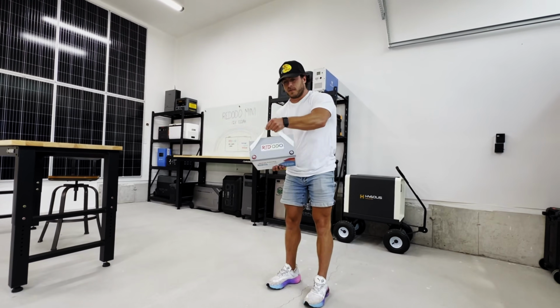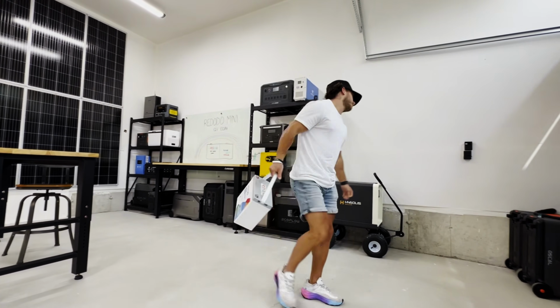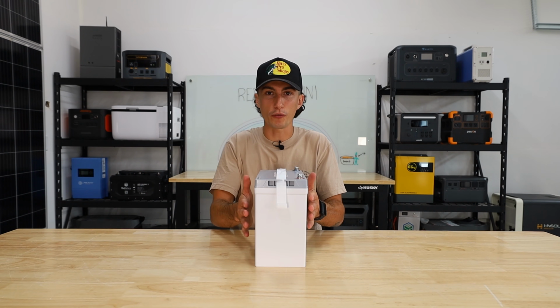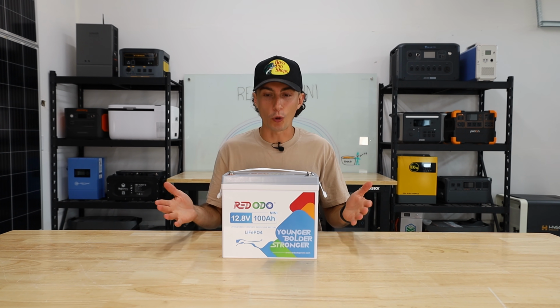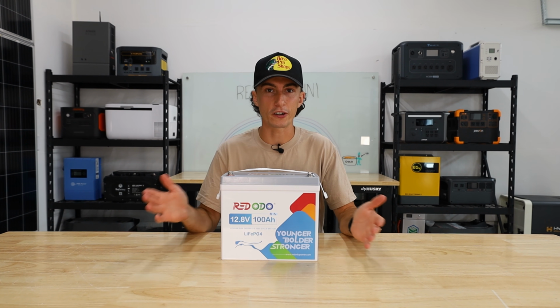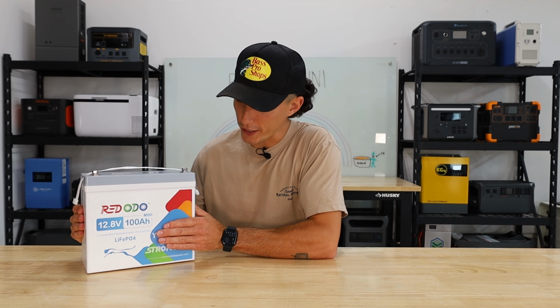This tiny thing weighs 19 pounds, so it passed the tiny baby lift test with flying colors. It's worth noting this is the Mini, so it has a much smaller footprint and is a lot lighter than the normal 12-volt 100 amp battery. It's a 12-volt 100 amp hour battery, making it a 1280 watt hour capacity, and it's rated to charge and discharge at a continuous rate of 100 amps. It does have a max discharge of 250 amps for 5 seconds, but we'll get to that later.